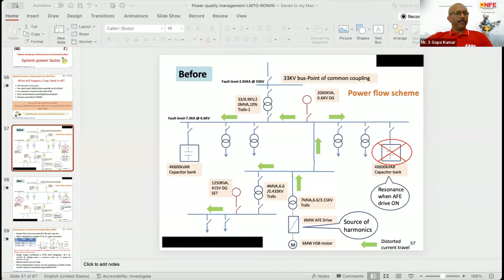If you see here, at the 13th component it was found that there is a heavy resonance. So at the 13th component it is required to design a filter or a choke to dampen this resonance and nullify the problem. But here the problem was the cost. Why I am bringing this point is that many times OEMs take disadvantage of the end user and customer if they are not aware. For just a 1 millihenry or 2 millihenry choke design, the cost was around 1.5 crore.